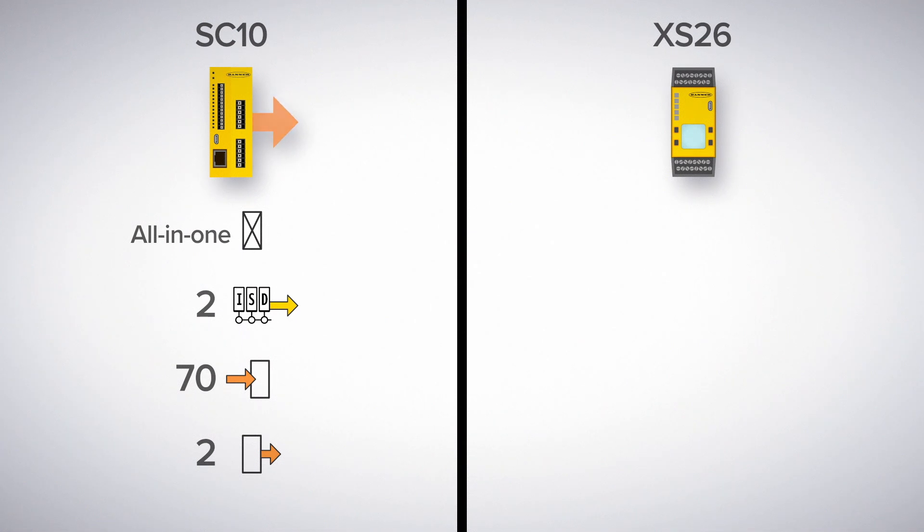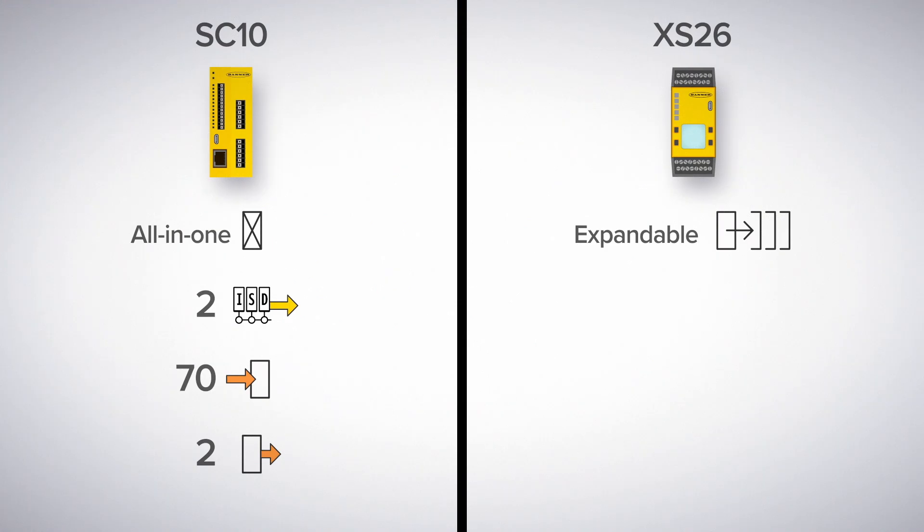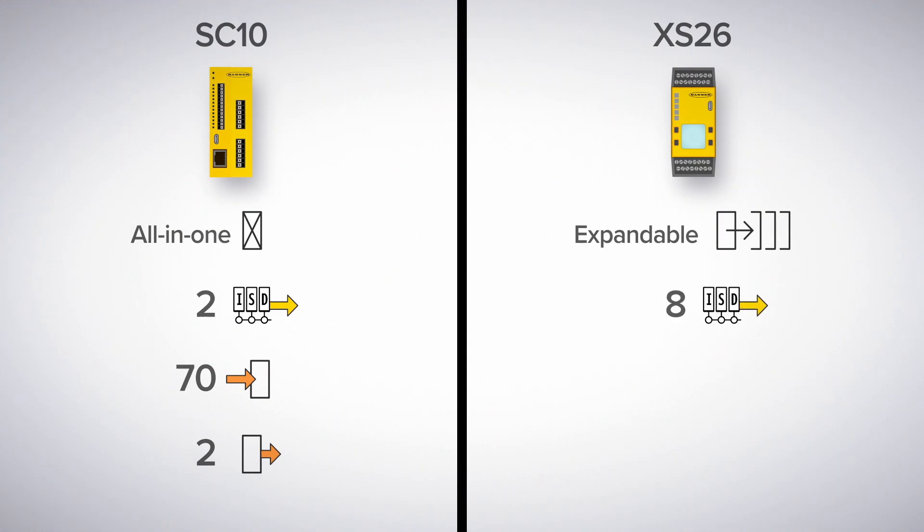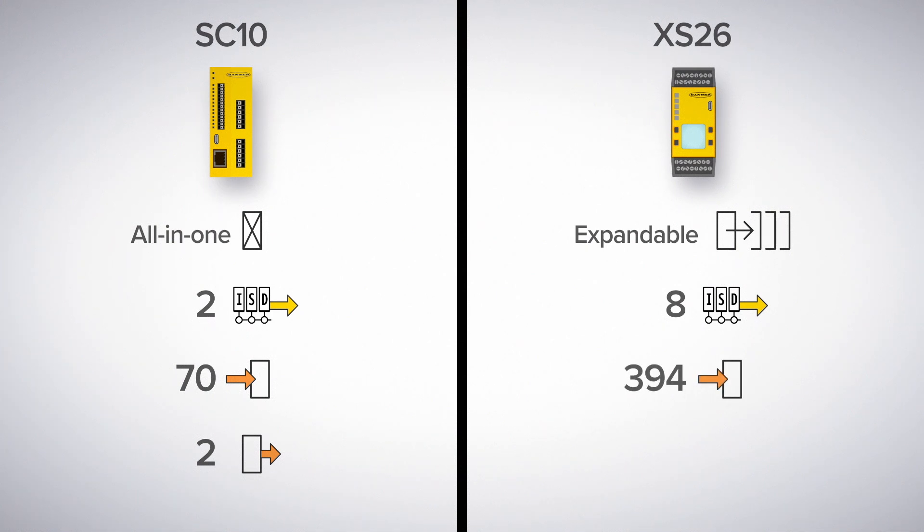The XS26, on the other hand, is expandable based on your needs. It can support up to eight ISD chains, totaling 256 ISD devices. Combined with standard safety inputs, the system can support up to 394 safety devices, and has up to 68 safety outputs.